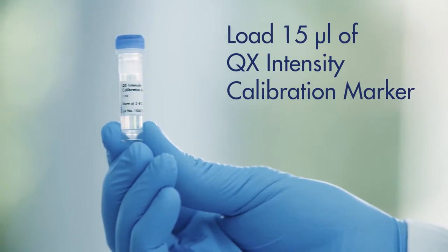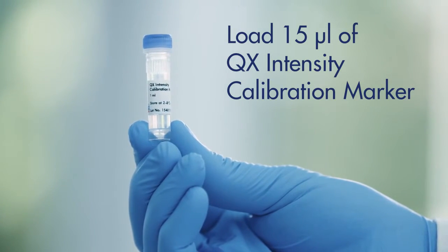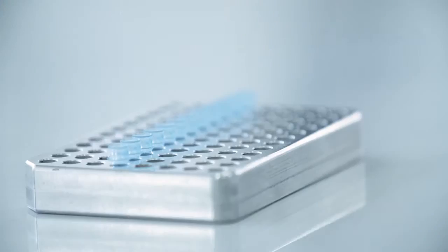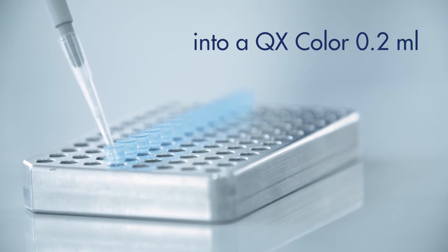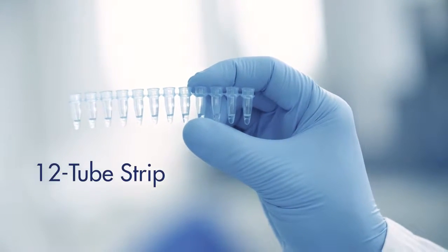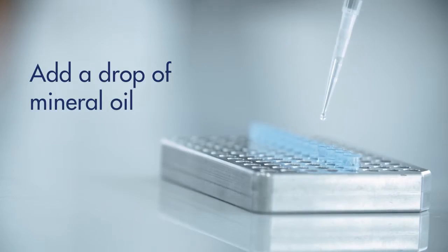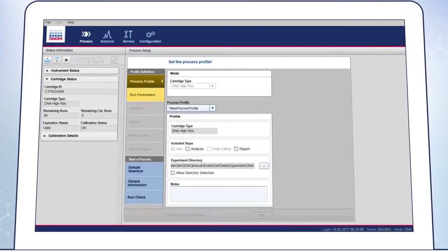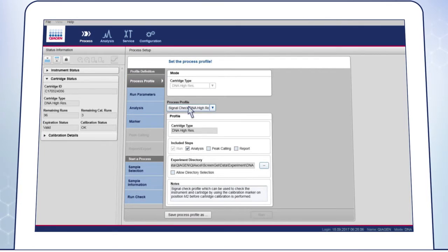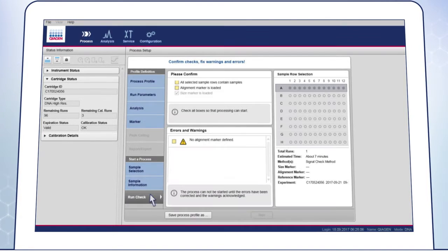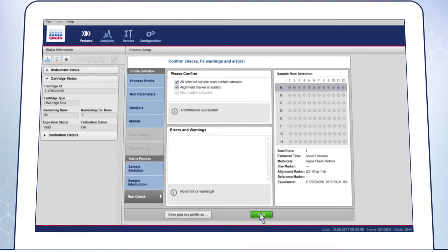For signal check, load 15 microliters of QX intensity calibration marker into a QX color 0.2 milliliter 12-tube strip. Add a drop of mineral oil and insert the strip into the marker 2 position of the buffer tray. Go to the process environment. Under the Process Profile tab, select the cartridge type and the default Signal Check Process Profile. Go to the Run Check screen, enter the required information and click on Start Run.